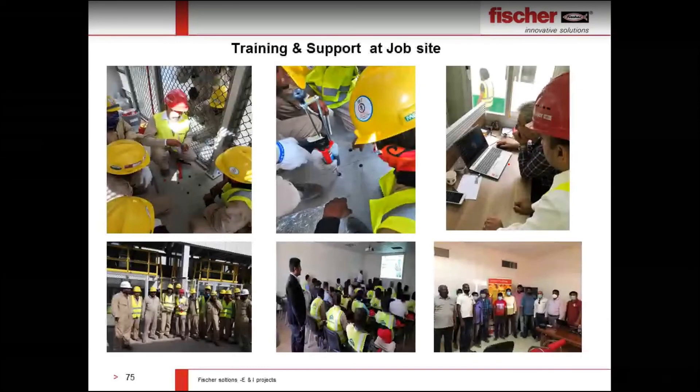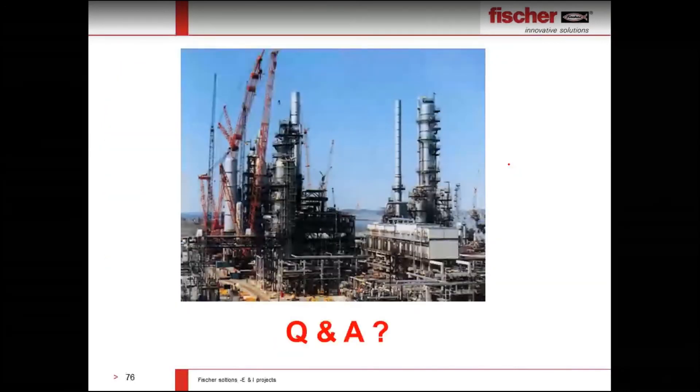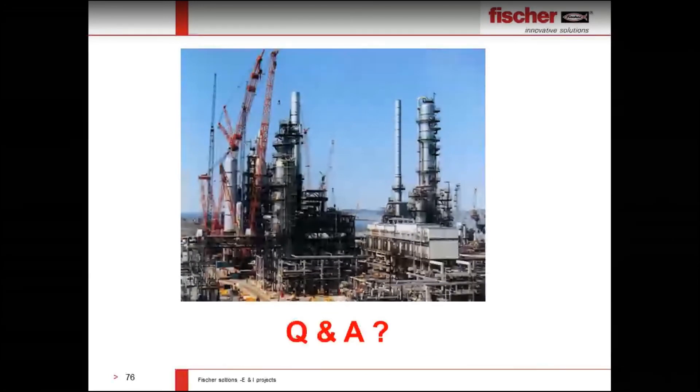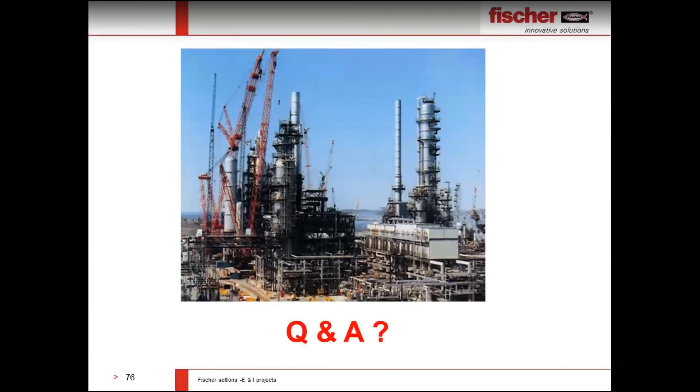With this, I conclude my presentation. During the Q&A, one question received: Will HDG damage anchor threads, and can you suggest solutions for anchors in harsh marine zones that rusted quickly? For marine environments directly exposed to seawater, you need to use high corrosion resistance anchors — HCR anchors. Regarding thread issues with HDG, the thread is normally undersized and the nut oversized, so you will see a small play in HDG threaded rods, which is permitted to avoid difficulty engaging threads. For marine exposure, we recommend HCR anchors or duplex stainless steel.